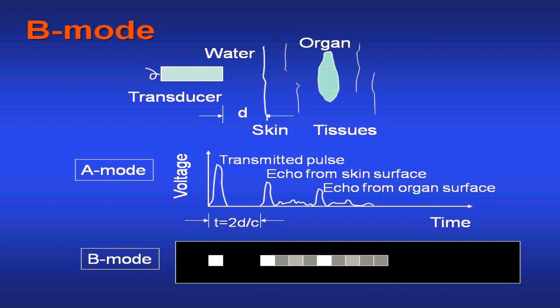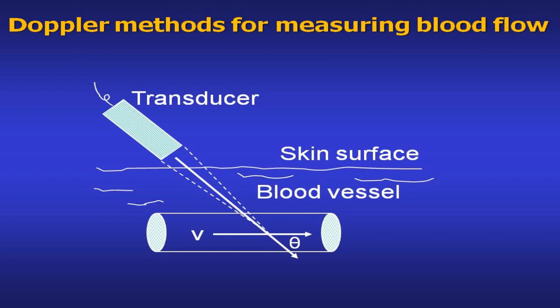So that's a very simple review of the physical principle involved. A unique feature of ultrasound is that it's capable of measuring blood flow. The Doppler principle is: you have a transducer over here, and you have blood flowing in a vessel, and this blood flow direction makes an angle of theta relative to the ultrasound beam. Because the blood is flowing, there is a frequency shift from the blood, which in this case serves as a reflector. This frequency shift can be detected by the same transducer, and from this Doppler frequency shift you can measure blood flow. That's a very unique capability.